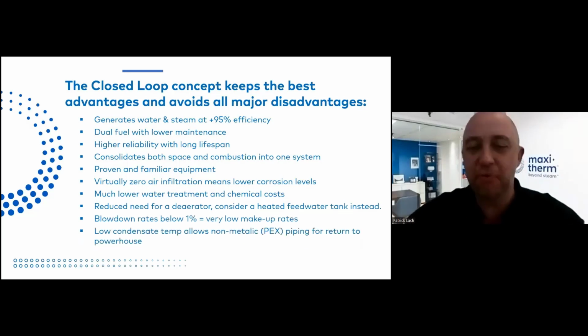Okay, so that's the point I was looking for in my head when I said, okay, let's move on. When you bring back low temperature condensate, you can consider using non-metallic condensate piping instead of Schedule 80 pipe. And that's exactly what is happening in certain areas now. They're considering using this because we can bring, at all times and in all conditions, low temperature condensate back to the boiler room. So non-metallic will live forever.